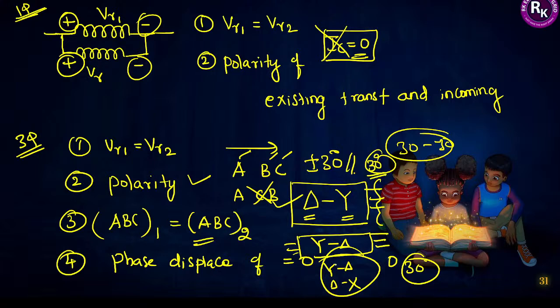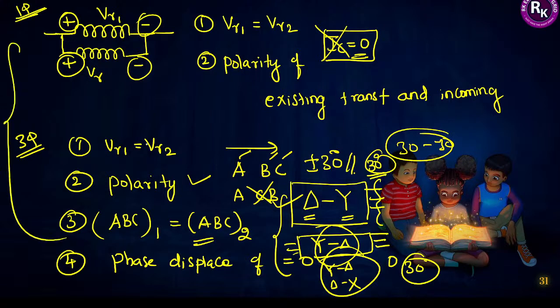You can expect this type of question often in upcoming exams. If the existing transformer is delta-star, the perfect matching for the incoming transformer is star-delta. If the existing transformer is star-delta, the incoming transformer should be delta-star. These are all the mandatory conditions to perform parallel operation for both single-phase and three-phase transformers.